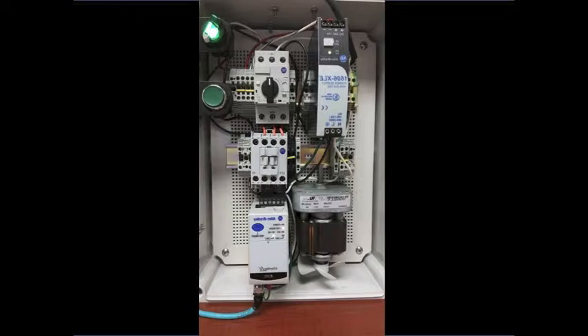When we stall the motor by holding the fan, that current will surge and increase. That overload current will be seen in the web server and Studio 5000 demonstration later in this video. After a certain amount of time, the E300 overload relay will overload and turn off the contactor.